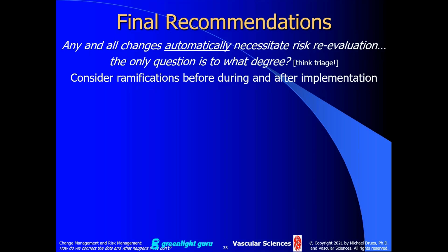On the other hand, when you get to the final implementation, this is, to me, the most basic tenet of the design controls. You want to do your final V&V testing, your final verification and validation testing, on your design freeze device. Now, that's what the theory says. That's what the regulatory textbook says. That doesn't always happen in reality, but that's what the theory says. But when you make a change, now you have to do at least some, maybe all, of that V&V testing over again. That's part of your risk reevaluation, proving it.